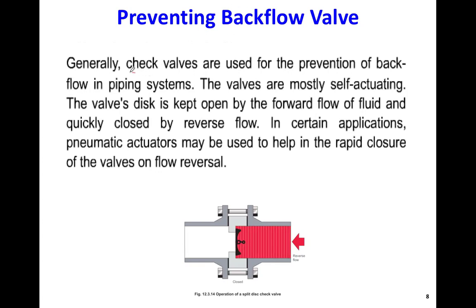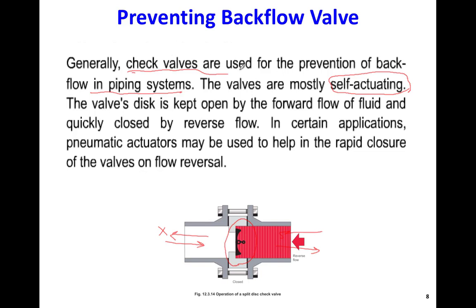A check valve is used to prevent backflow in the piping system. They are self-actuating — meaning they are designed to open and close by themselves depending only on the direction of flow. When the flow is from left to right, it's open; when it's from right to left, it will be closed. It is a self-actuating valve that works by itself and most of the time does not need any external force, energy, or help.